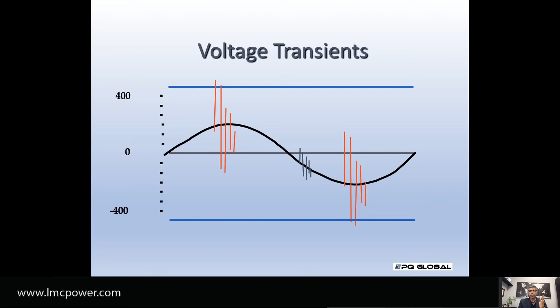So these are the problems that are coming from the outside. Basically what we're seeing is a lot of energy riding on top of the sine wave, high frequency, riding on top of low energy, 60 hertz. And that's going to try to find its way to go down to ground in any way that it can. So anything from the outside coming in, large amount of energy, we're going to try to create some kind of drain at the input of the building to protect against the outside. Or else it'll go inside the building.